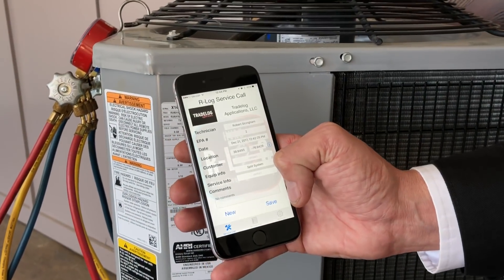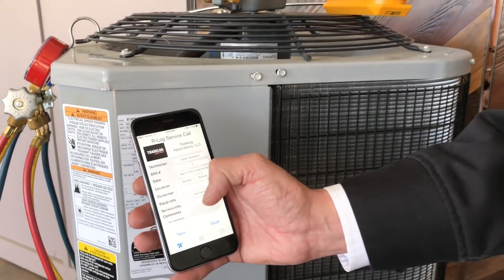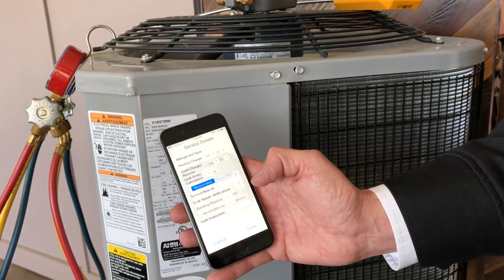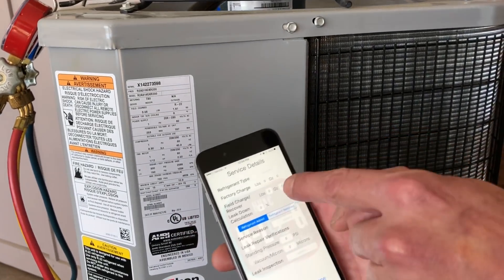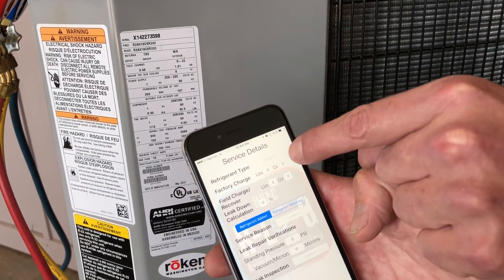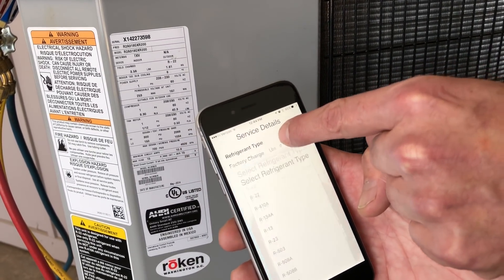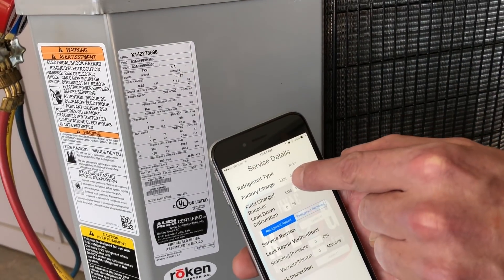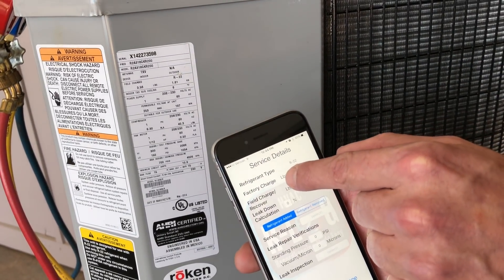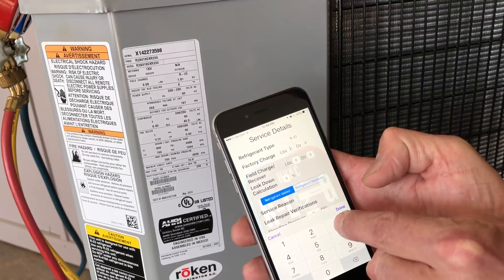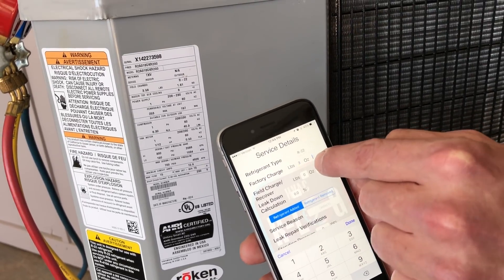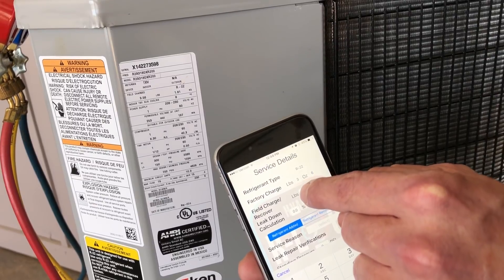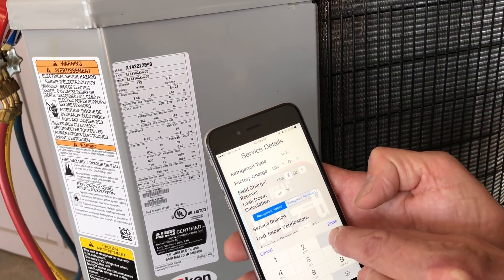So that's done — record-keeping made easy. For service info, we hit the button and type in our refrigerant type from the data plate, which is going to be R-22. Then we type in the factory charge. Technically, this is a three pound under-five-pound system, so we would not need to keep records for this, but we're going to go ahead and do so anyway.